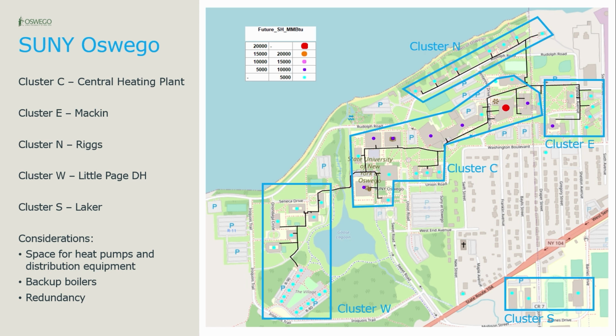When comparing the clustered approach to the centralized approach, we showed that if you get rid of central plants you might have to build new buildings, so you have to look at whether there's space in existing buildings for heat pumps that can serve all these buildings rather than just one. If you also want redundancy on those heat pumps, backup boilers, and peaking boilers, you're likely looking at building new central energy plants. Compare that to the cost of just the yellow connections of one large centralized system, laying pipes to connect these networks together.